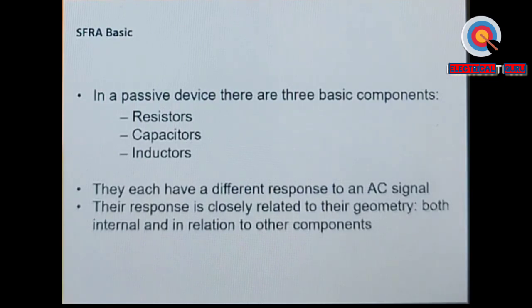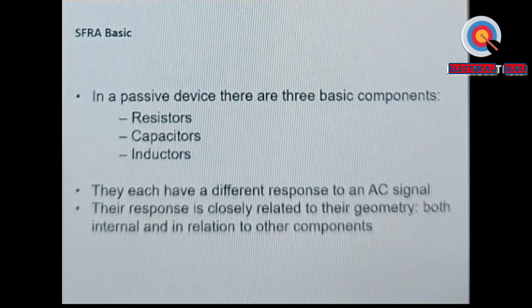The response is closely related to the geometry, both internal and in relation to the other components. This is a very important statement. Take a transformer winding per se, which has capacitance with reference to the tank, or if you take it between R and Y phase, then between the phases there is also insulation, and because of that there can be a capacitance between them. So the relative position of the winding with reference to the tank or another phase winding can have an influence on capacitance or inductance measurements, and when we measure it, the response can reflect that.